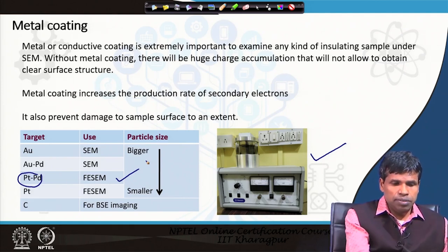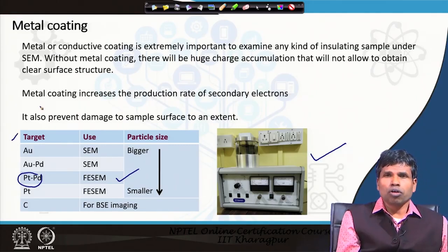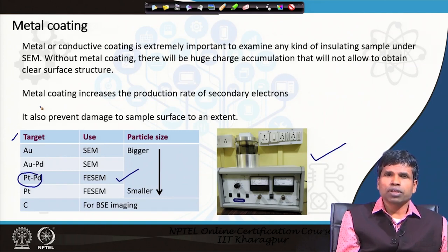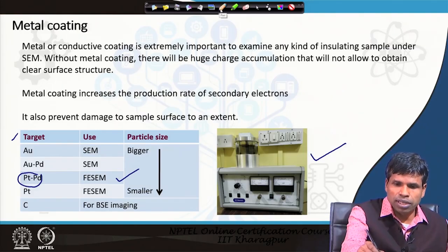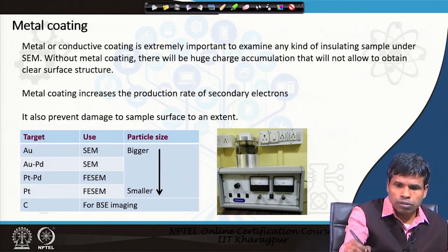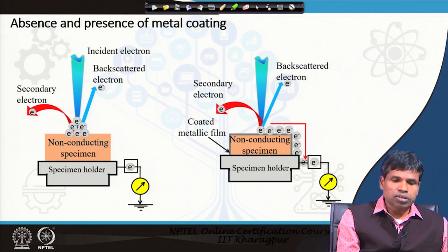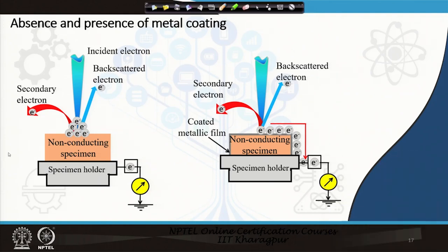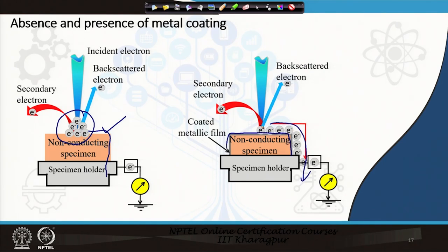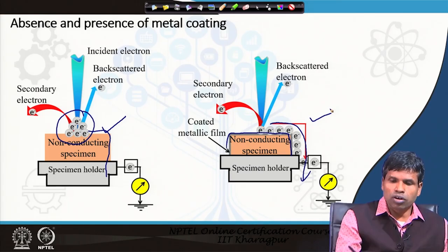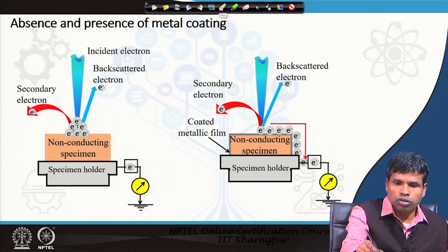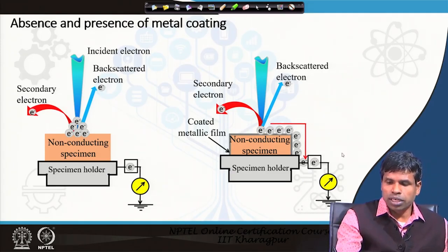In the absence of metal coating, electrons accumulate on the non-conducting sample surface because they cannot pass to ground. With a metal coating provided, electrons are not accumulated at the sample surface, giving us a clear surface image. Metal coating is very important for all non-conducting samples; without it we cannot see a clear surface image.